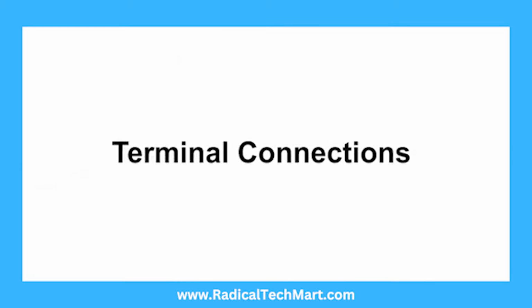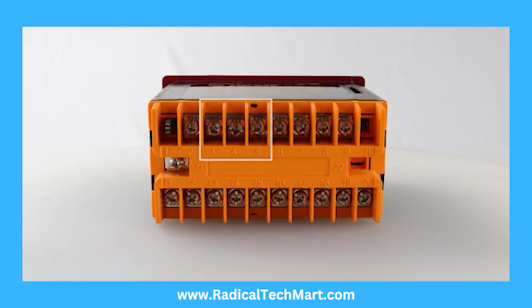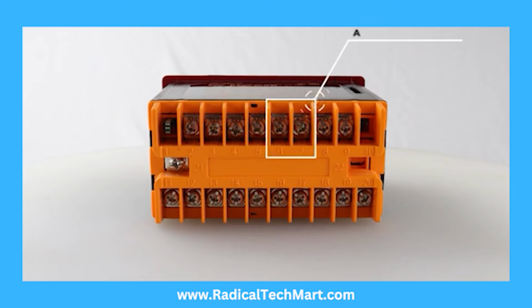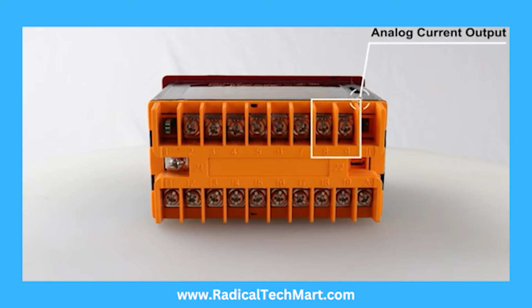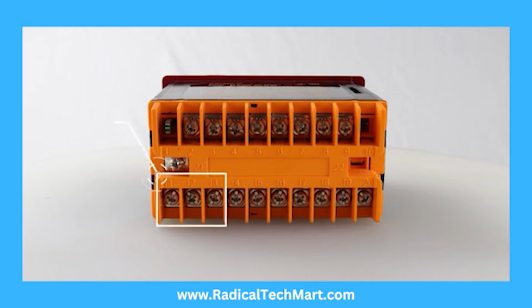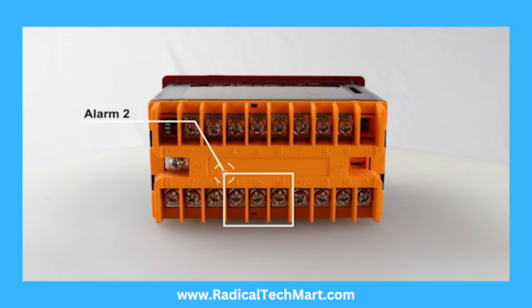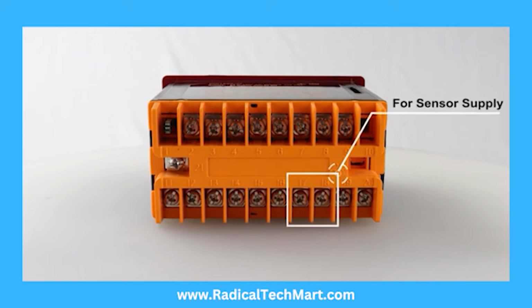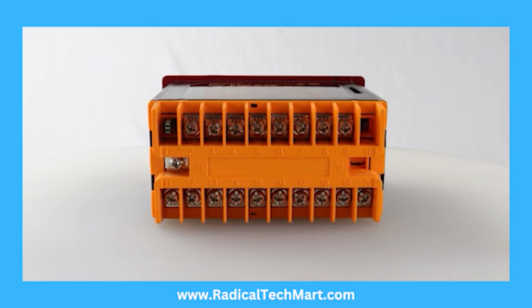Terminal connections. It has 22 terminals. Terminals 3, 4, and 5 are used for input signal, which can be either thermocouple, PT100 or analog inputs. Terminals 6 and 7 are for analog voltage output. Similarly, terminals 8 and 9 are for analog current output. Terminals 11, 12, and 13 are used for alarm 1. Similarly, terminals 14, 15, and 16 are used for alarm 2. Terminals 17 and 18 are for inbuilt sensor supply, plus 24 volt for providing power to transmitter. Terminals 19 and 20 are for auxiliary supply.